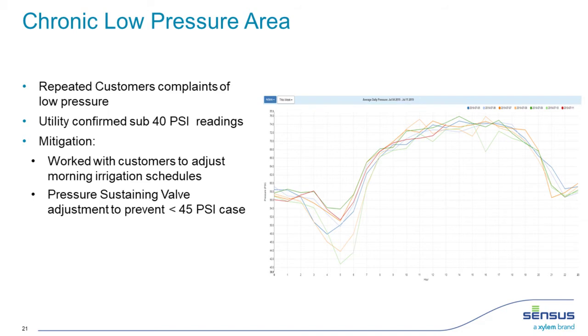Yeah, the issue all distribution systems have is we get the phone call, I have low pressure. Typically, as everybody knows, it's usually a volume issue and not a pressure issue. But in this case, this is a pressure issue. So in the past, you'd roll that truck out there, you'd say yeah, it is low pressure. The problem is you cannot see the impact area. That's what we've seen on so many of our issues that we found we had issues with - how big is this issue, where is it, and how are we going to deal with it? Because if you don't have that information, we can't reach out. We would have never known that the cemetery was causing this pressure drop way up in our system. It's quite a distance away from it.